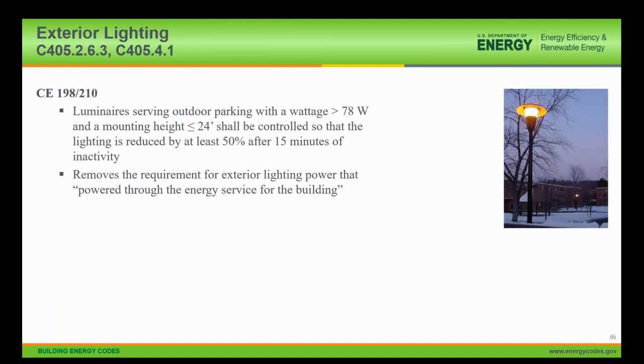Finally, exterior lighting. So luminaires that are serving the outdoor parking area that have a wattage greater than 78 watts and a mounting height of 24 feet or lower shall be controlled so that lighting is reduced by at least 50% after 15 minutes of inactivity. The reason why those values are 78 watts is really near the threshold of where cost effectiveness applies. The 24-foot is also a limitation of some current devices and how well they can detect occupancy. When you start moving into the 30 and 40-foot mounting heights of typical light fixtures in some applications, certain sensors have some sensitivity issues. And so that's why it's set at those two values.